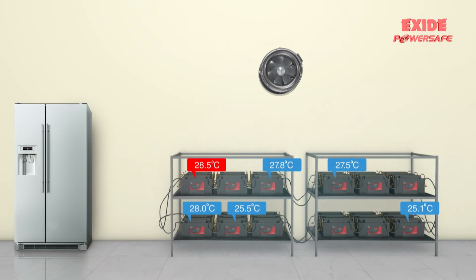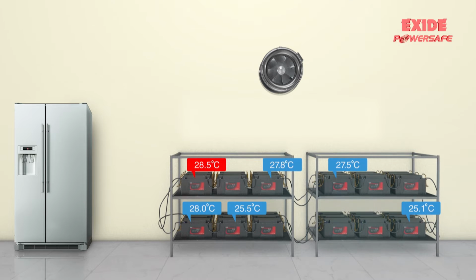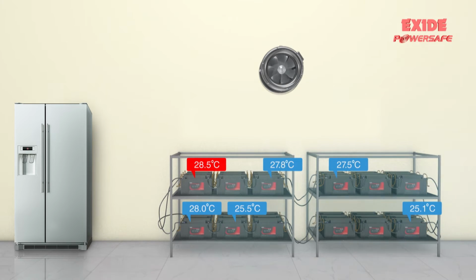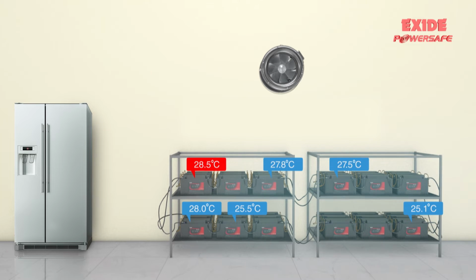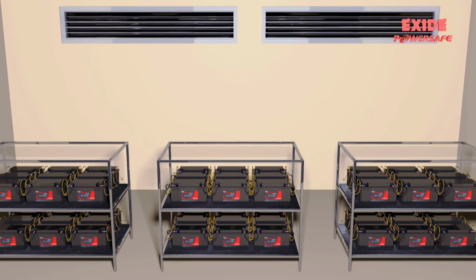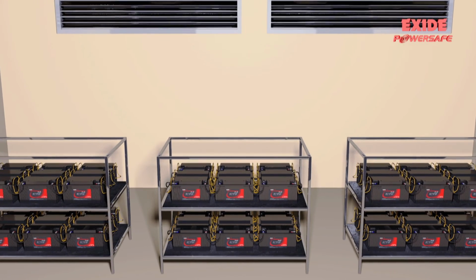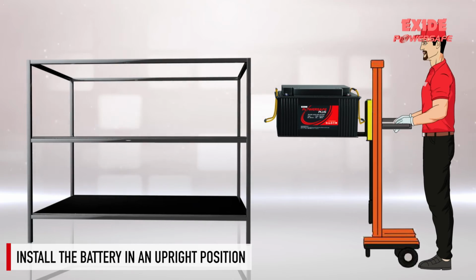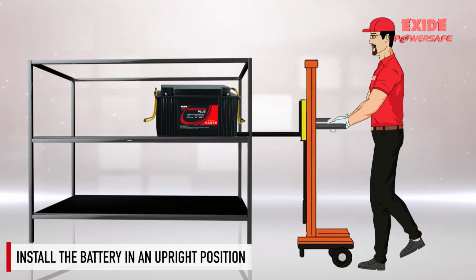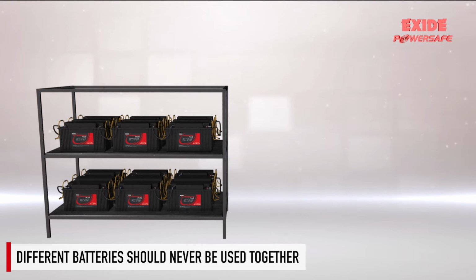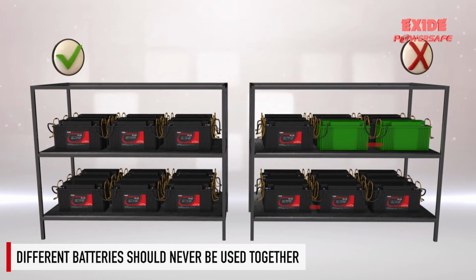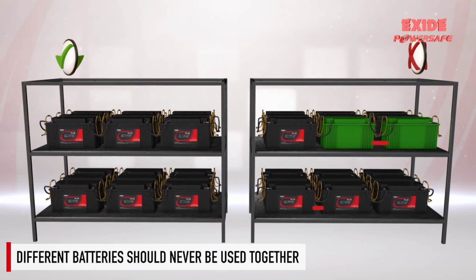The location and arrangement of batteries should result in no greater than a 3 degrees Celsius temperature differential between cells at a given time. Avoid conditions that result in localized heating or cooling, as temperature variations would cause the battery to become electrically unbalanced. The batteries should be mounted in a correct manner, such as: install the VRLA battery in an upright position. Batteries of different capacities, make or performances should never be used in the same bank.